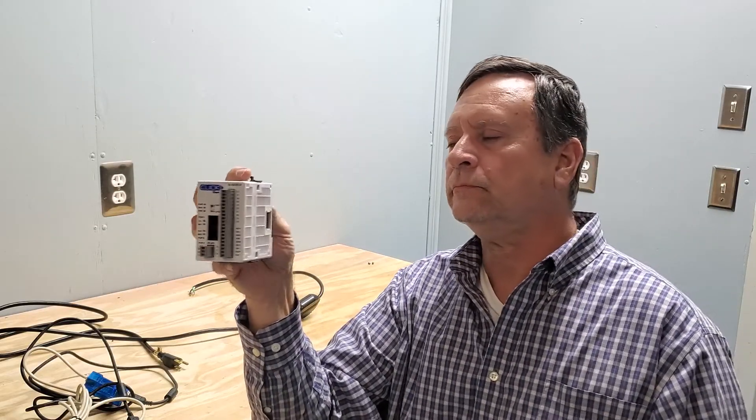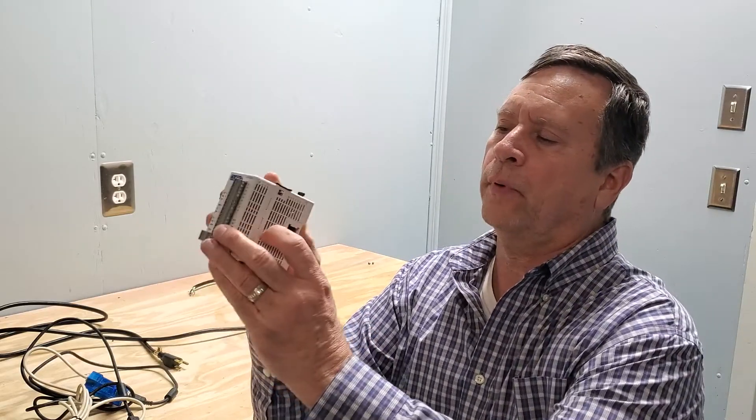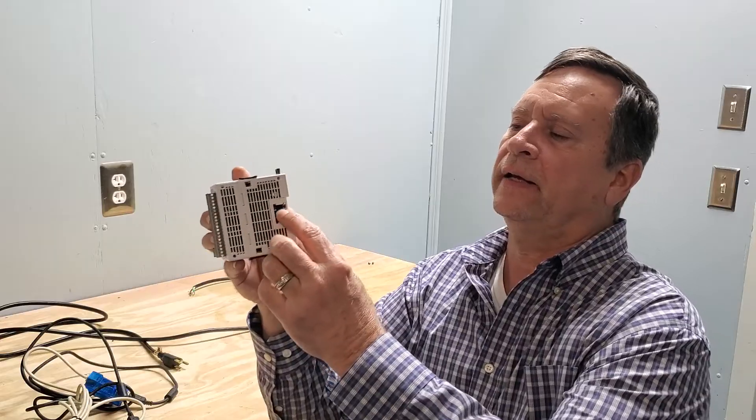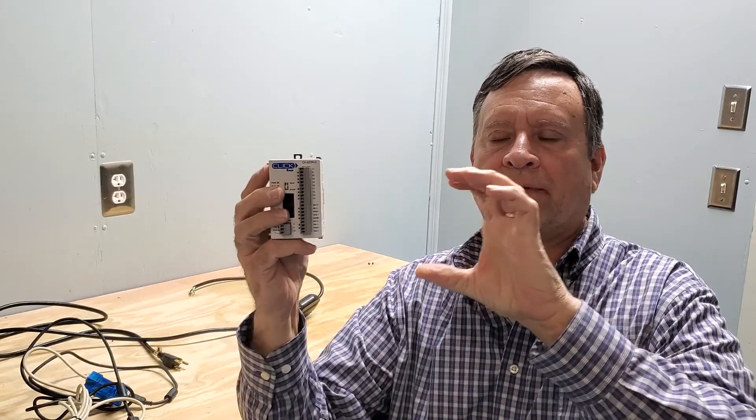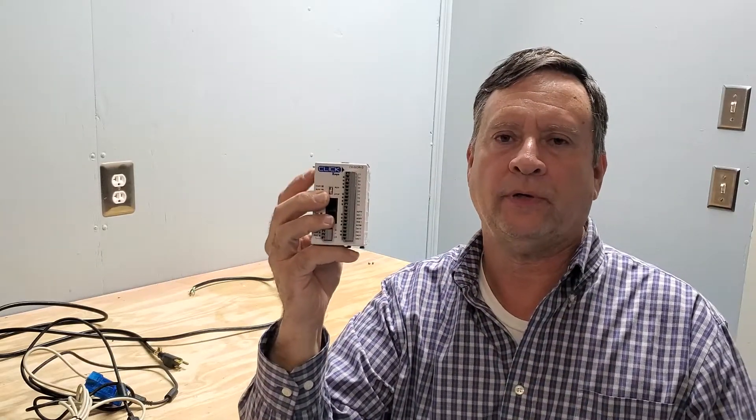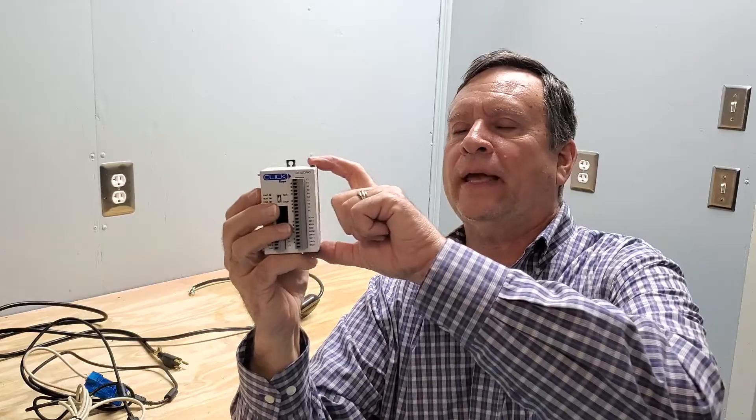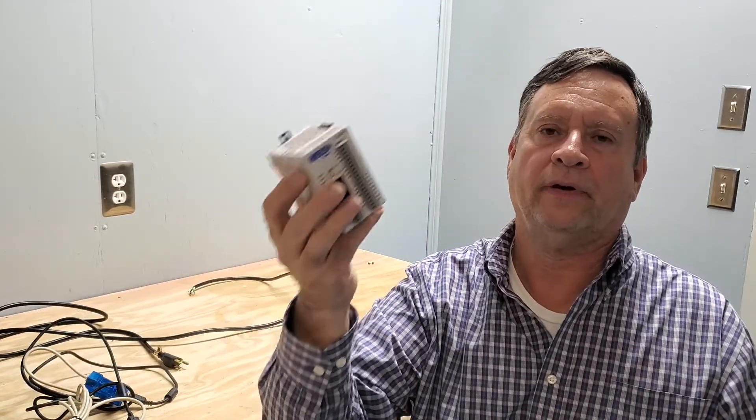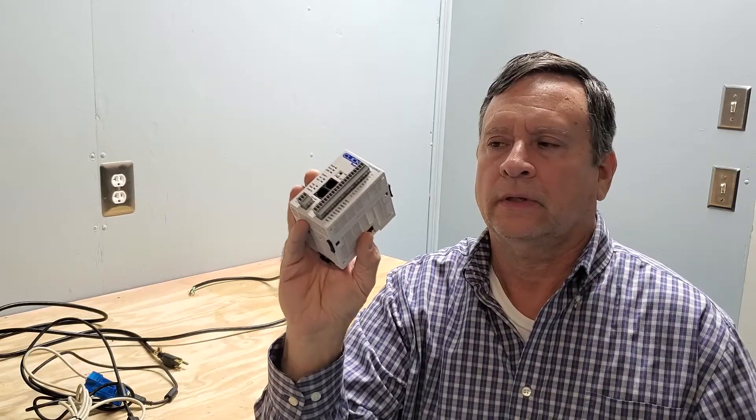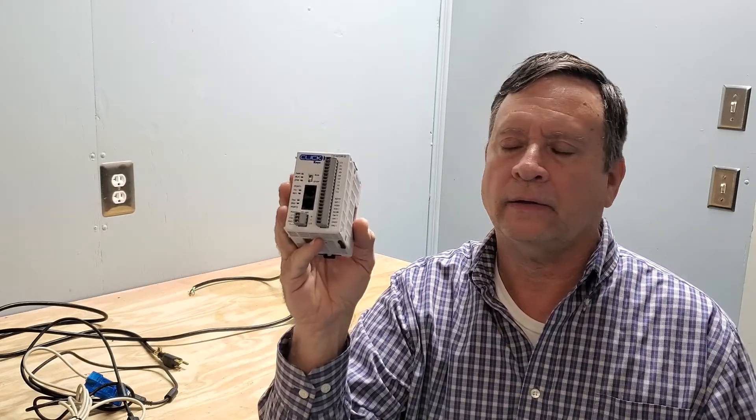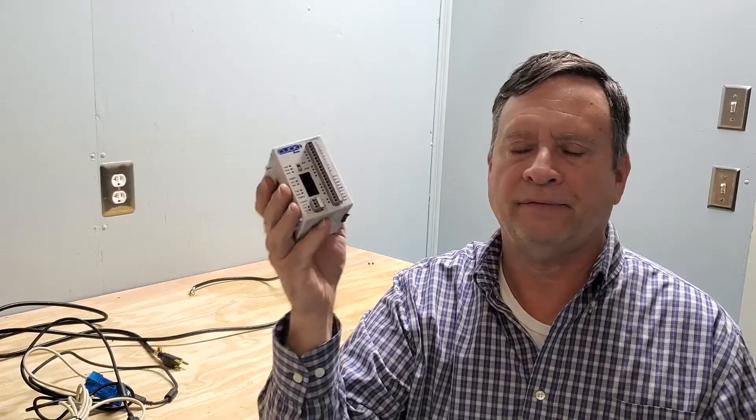These are stackable. This little port here on the side is actually a communication bus. You can have as many as eight more modules on the side of this connected, in each one communicating back to the CPU here. That would give you those other modules: input and output modules, relay modules, analog modules, and so forth. You could have as many as 150 inputs and outputs on this one little device.